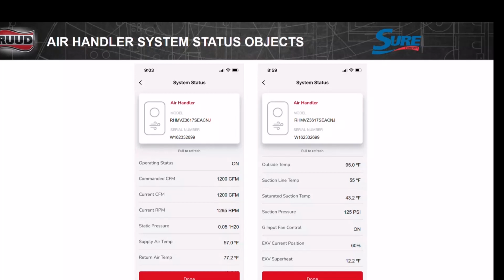It's showing your static pressure, but I guarantee that static pressure is not 0.05 right there. No way. That's probably pushing 1 inch of static. These things will tell on you, because it's taking the torque and the RPM of the motor and determining what the static is. And it's pretty close. I've measured with my gauges, and I've measured it by looking at the app, and it's pretty dang close.